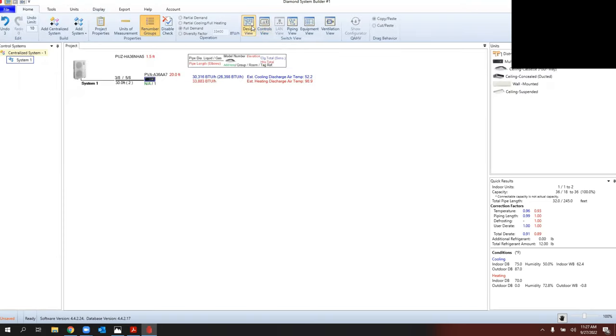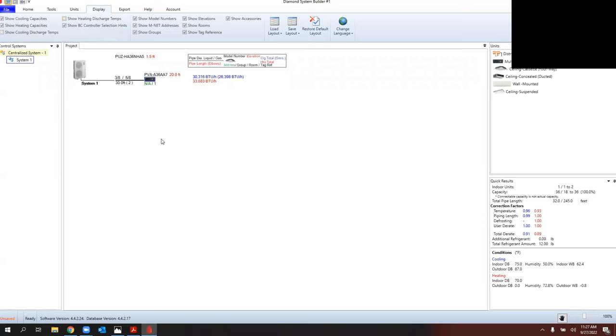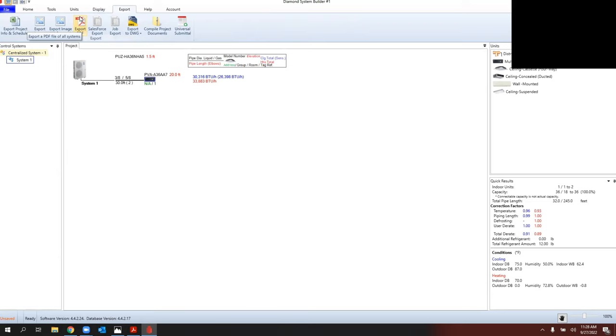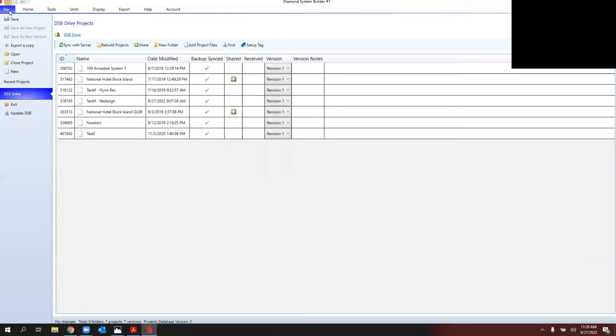If you leave everything checked in Display and give the report to a homeowner, it will show estimated heating discharge air temperature of 90.9°F and 52.2°F in cooling — which could cause problems down the road on service calls. I highly recommend unchecking discharge temperatures under Display. At minimum, you want to show cooling and heating capacities and model numbers. The PDF export is most common for a single zone; for multi-zone I'll export Project Info and Schedules, which gives a much better project stock list.